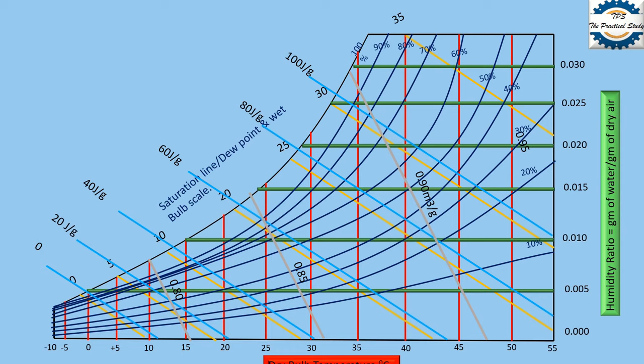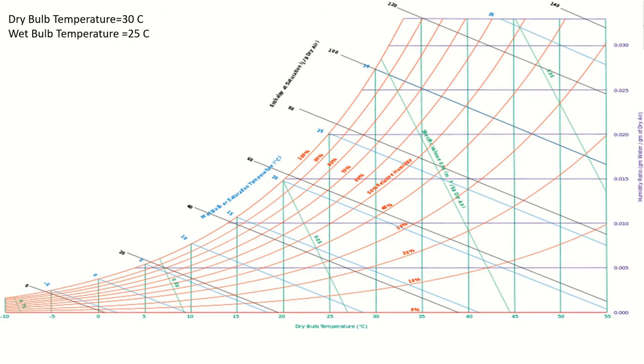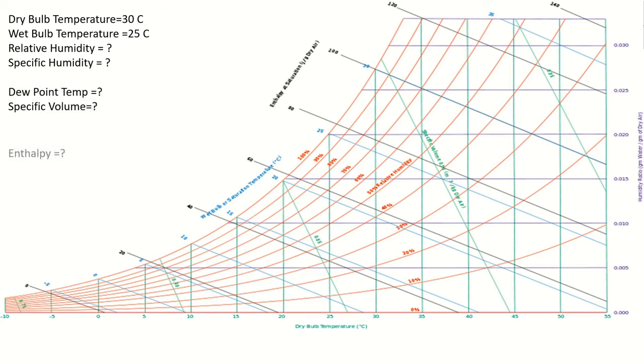Now it's time to solve a practical example of how to calculate required parameters on the psychrometric chart using a professional chart to get correct values. To use the psychrometric chart, you must have two known parameters. Given: dry bulb temperature is 30°C and wet bulb temperature is 25°C. We need to find relative humidity, specific humidity, dew point temperature, specific volume, and enthalpy.